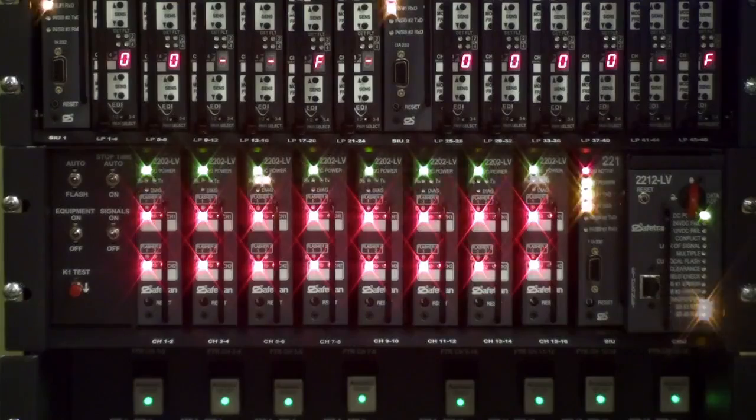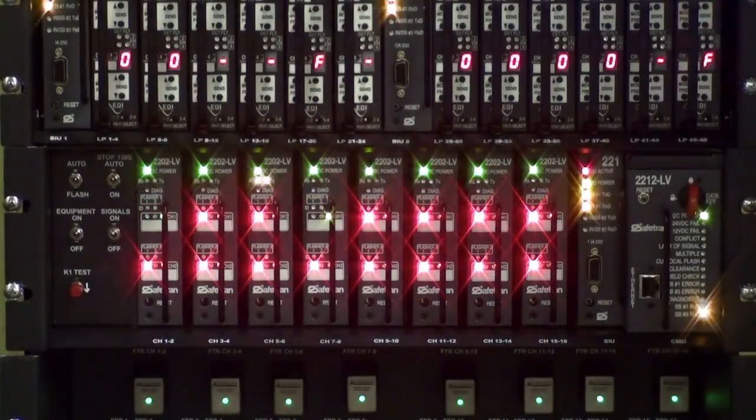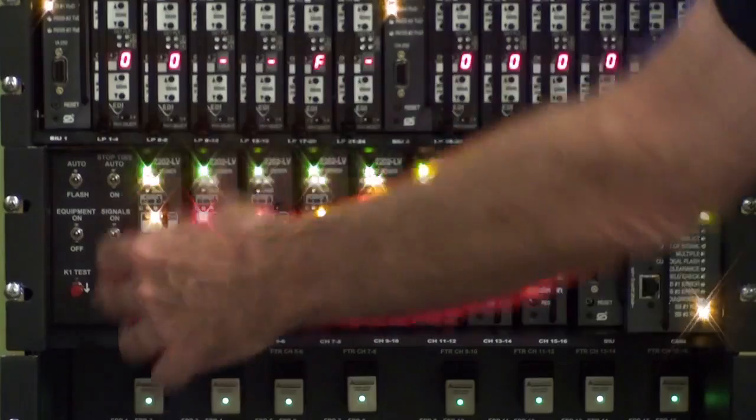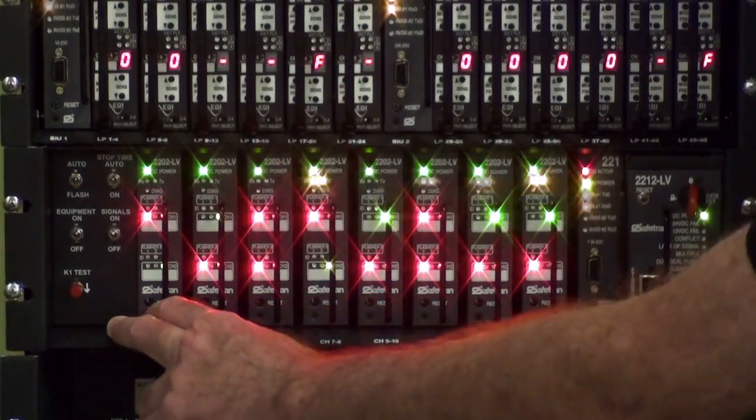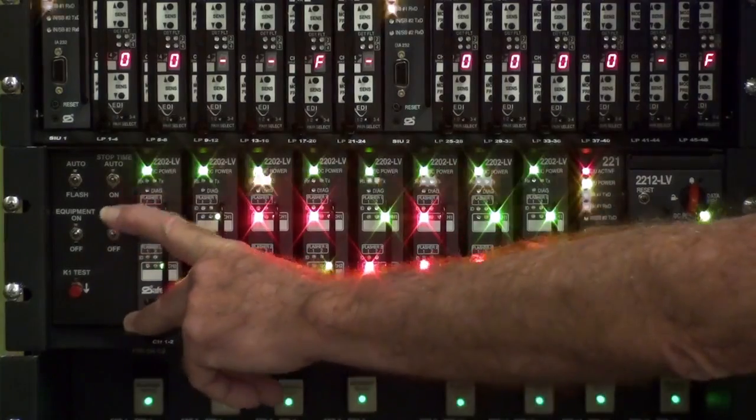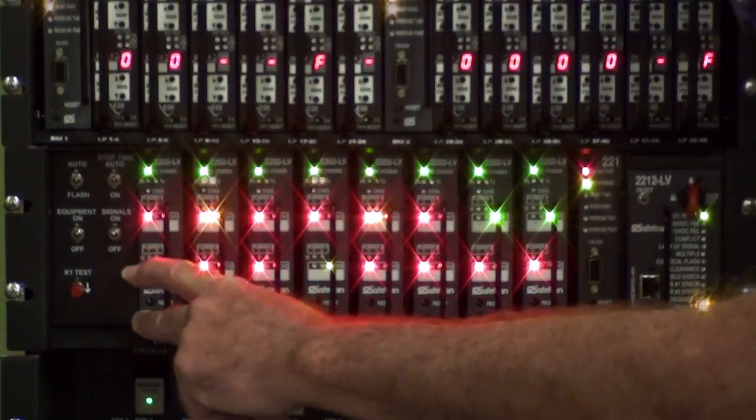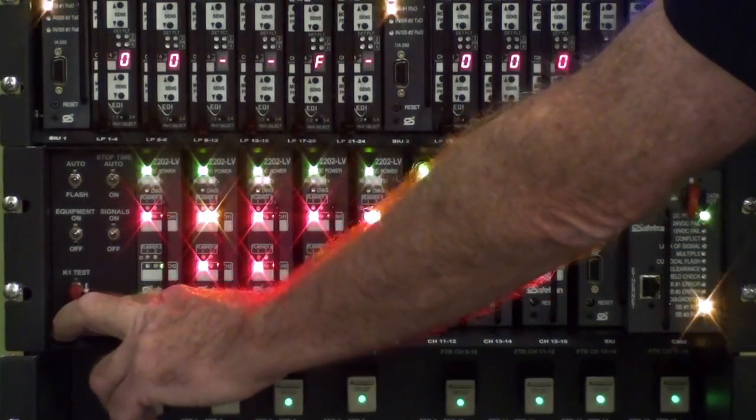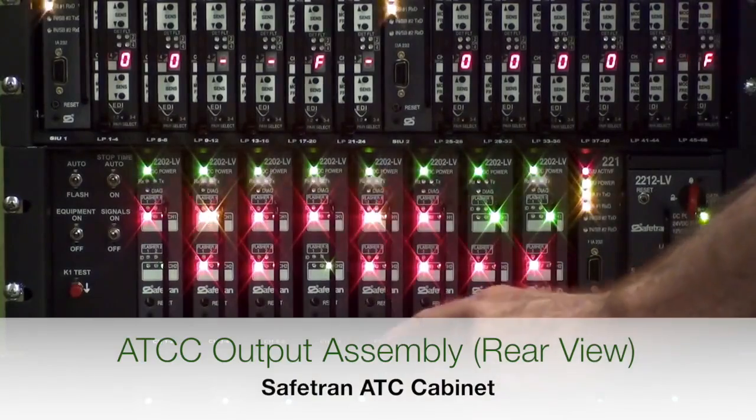Located on the front left side of the output assembly are the technician switches, as opposed to a NEMA cabinet, where they are located on the back side of the police panel. The switches include the auto flash, stop time, signals on-off, and equipment on-off. It also has this 24-volt DC test switch. This allows you to turn on the output indicators on the HDSPs momentarily to visually observe the state of the intersection when it went into flash. Additionally, the main contactor is located within the output assembly, directly behind the technician switches.